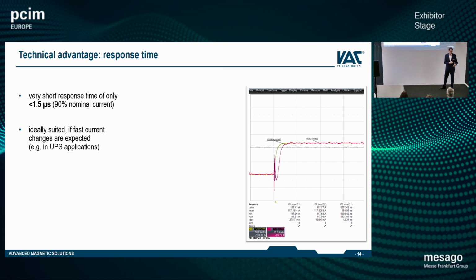The technical advantage of this flat response is also seen in the response time. What we see in this measurement is a current step where the primary current steps up, and you see how the sensor's voltage output follows. Here it's shown a bit larger - the primary current ramping up and the sensor output, and the time at 90% of the current step is the response time. For this new open-loop sensor series, the response time is smaller than 1.5 microseconds in this scenario. This means the sensor is also ideally suited for applications where the primary current changes rapidly, like in UPS applications.